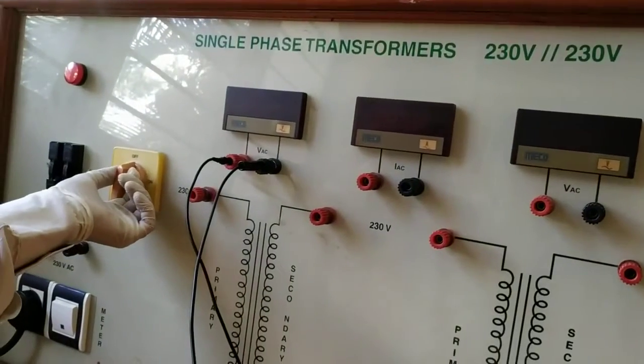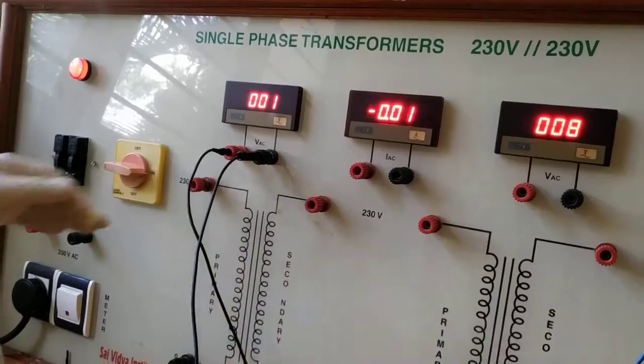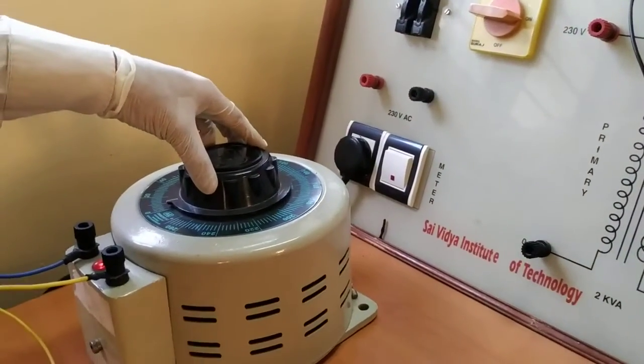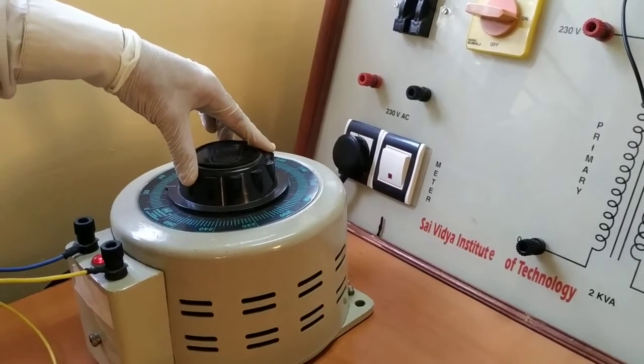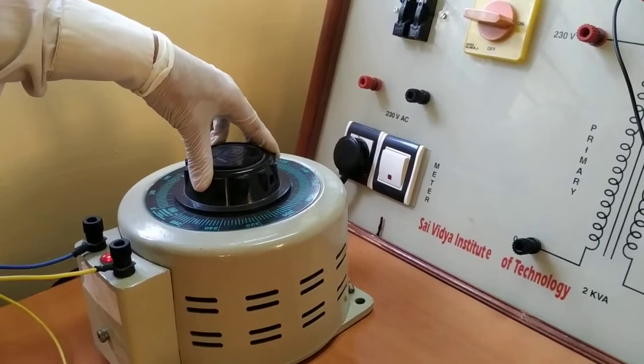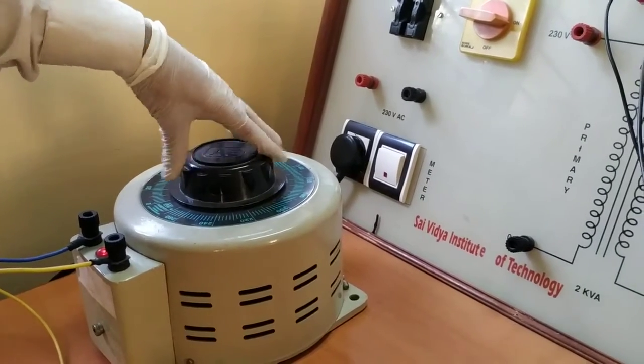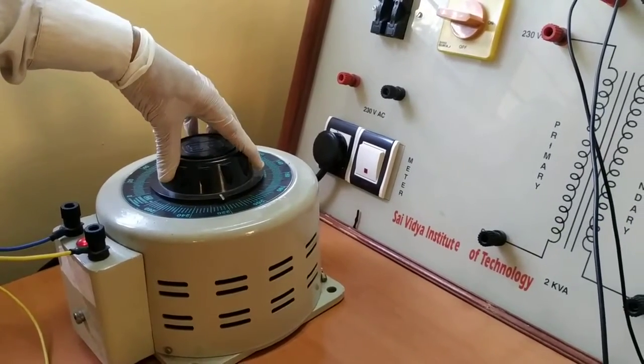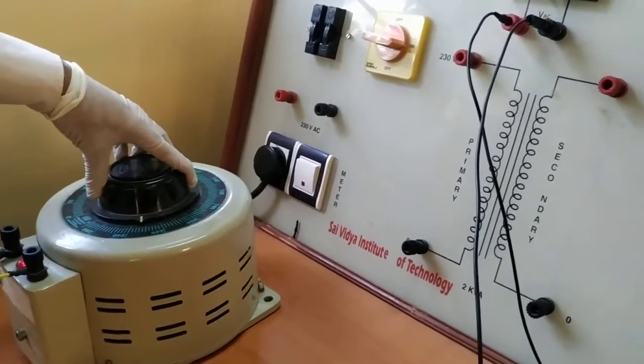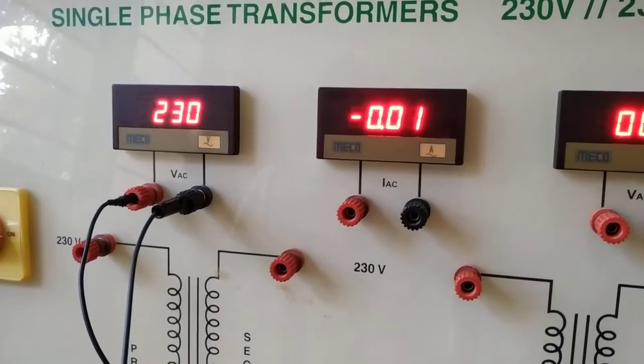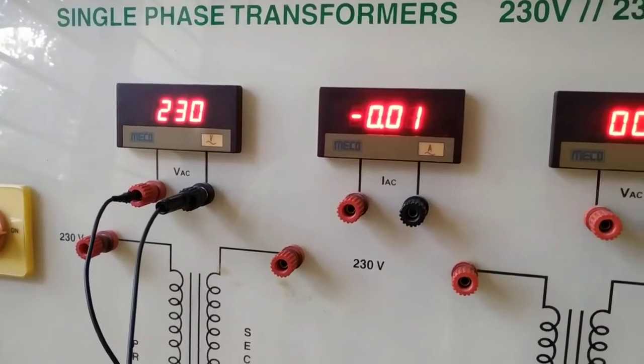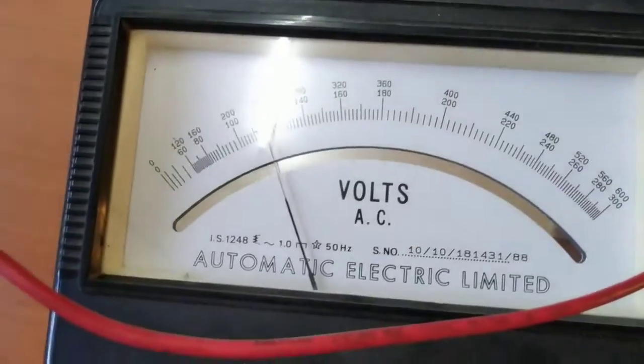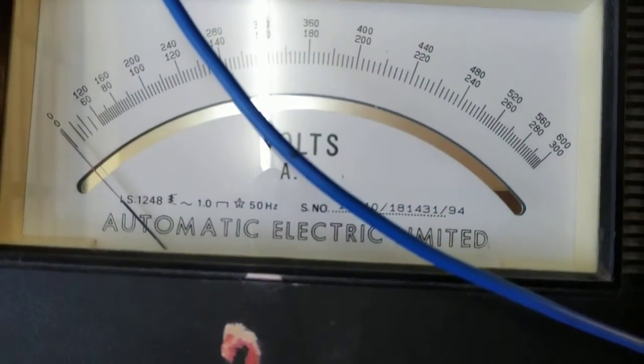After checking the configuration of the circuit, let us switch on the supply. Once we switch on the supply, we start varying the auto transformer gradually until we reach the rated voltage, that is 230 volts. Now we observe the readings of all three voltmeters. V1 is reading 230, V2 is also reading 230, while V3 is reading 0. Since V3 is reading 0, we come to the conclusion that it is subtractive polarity.